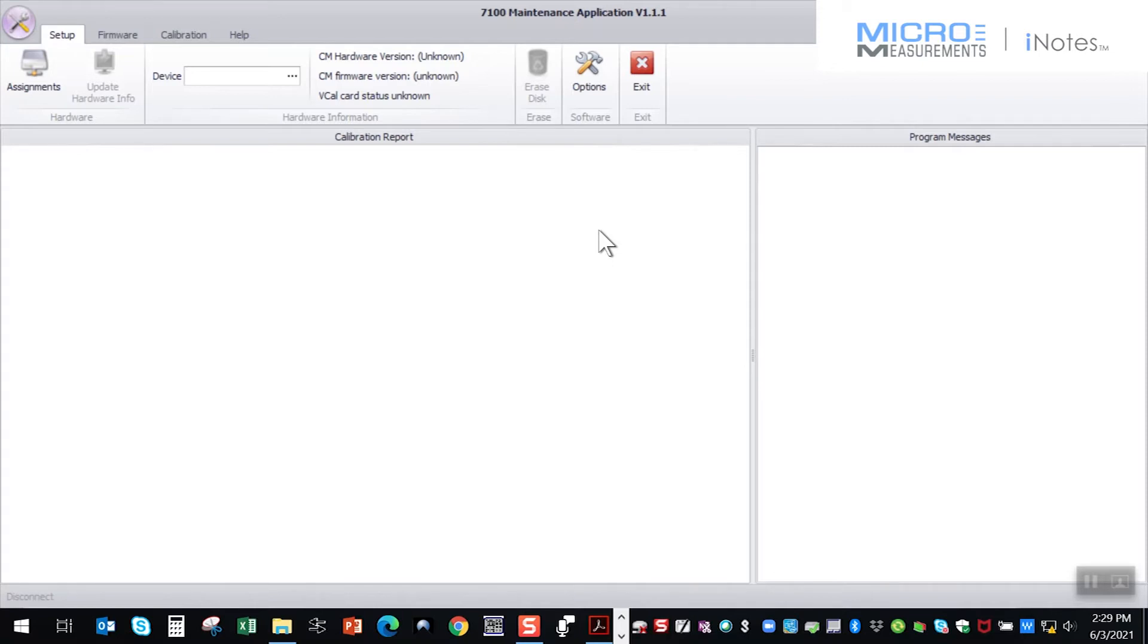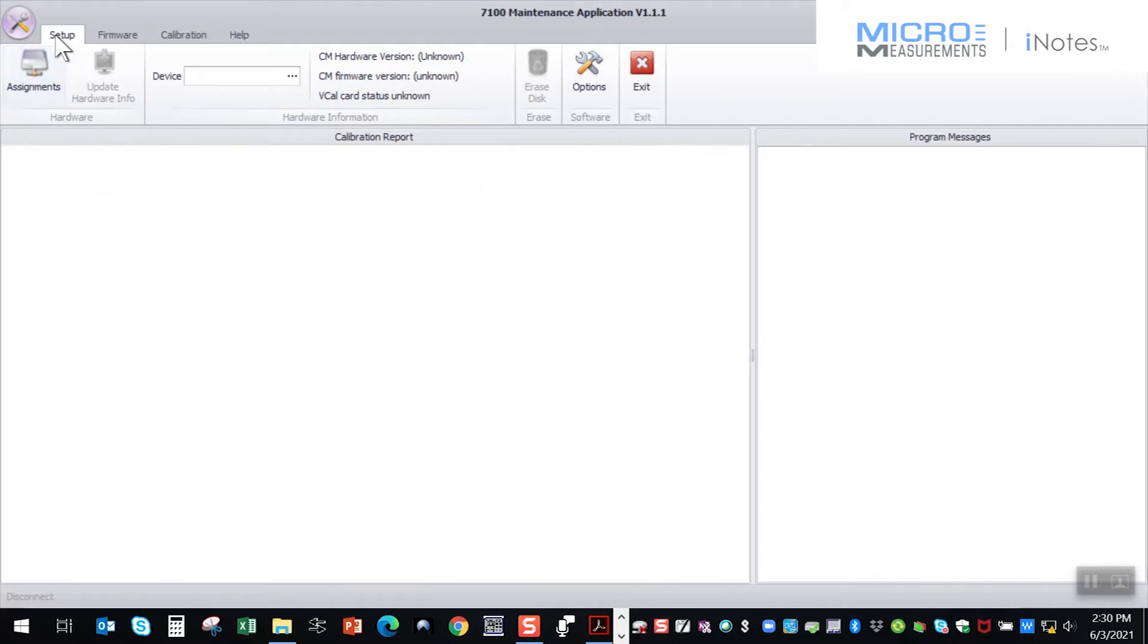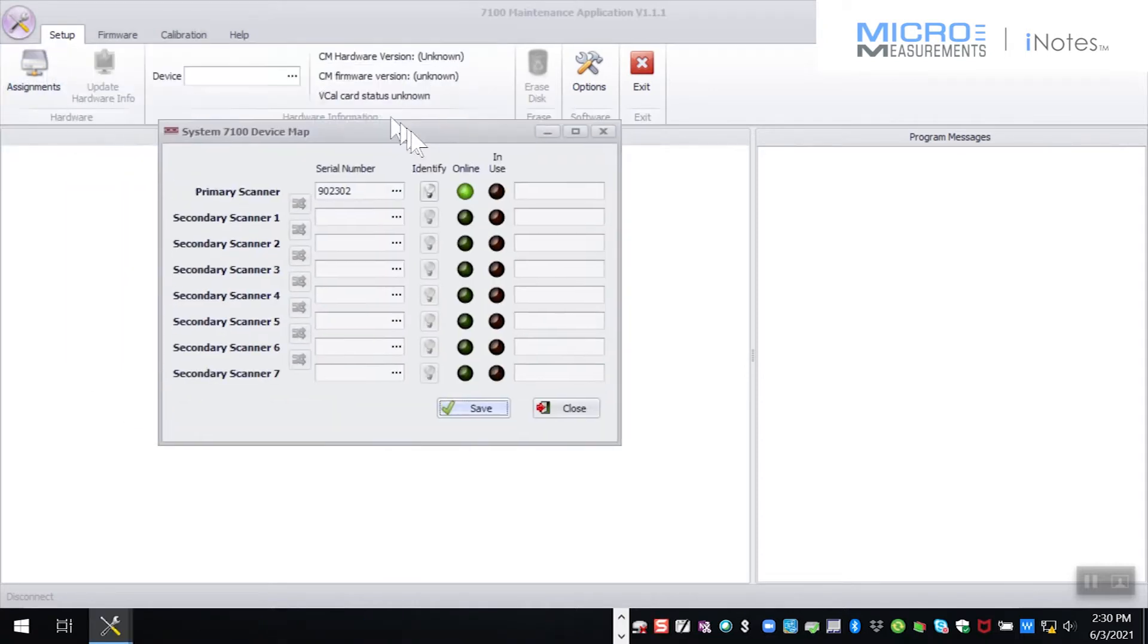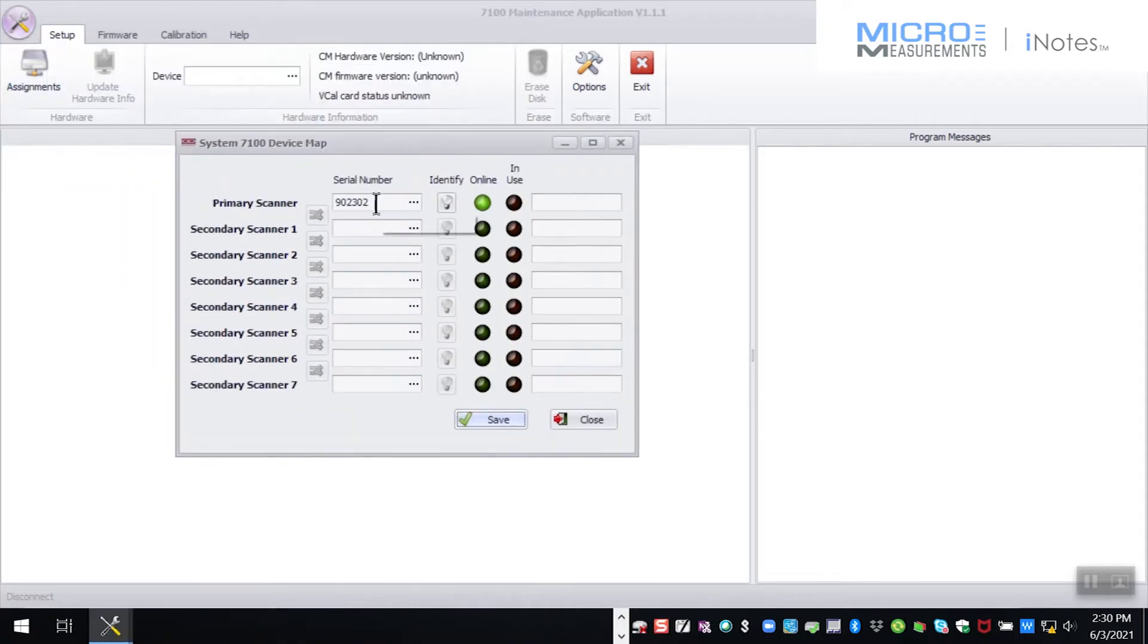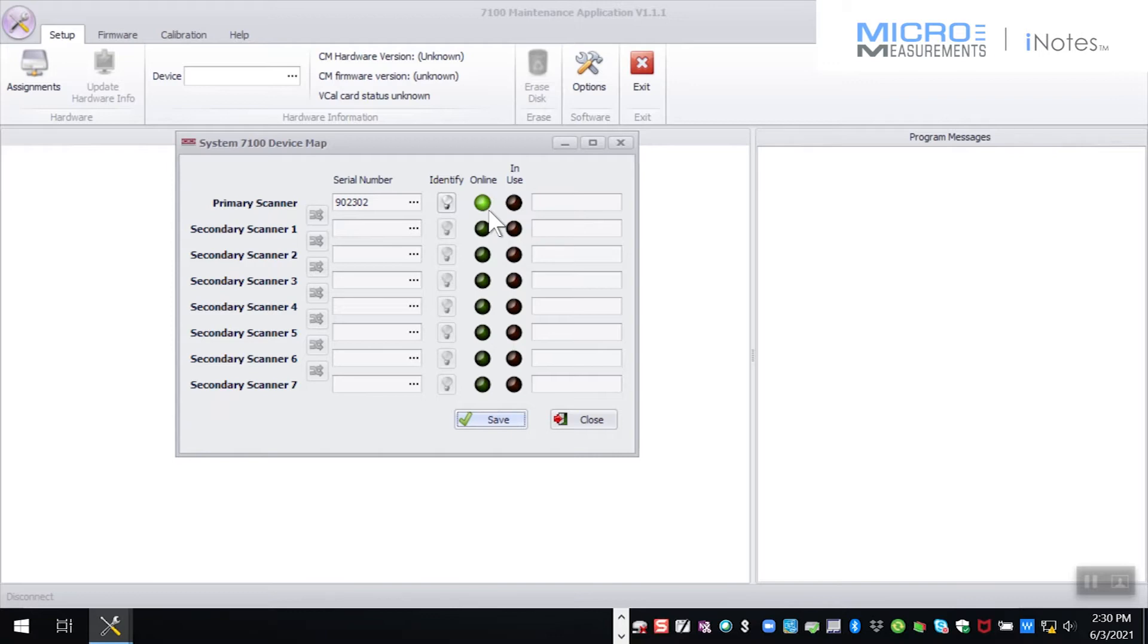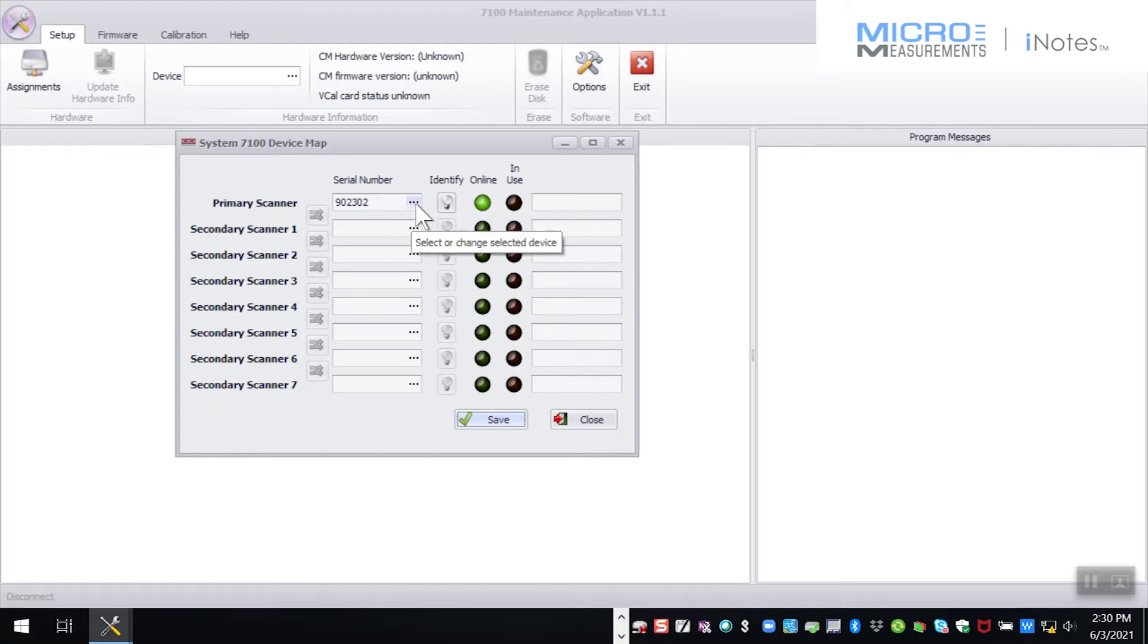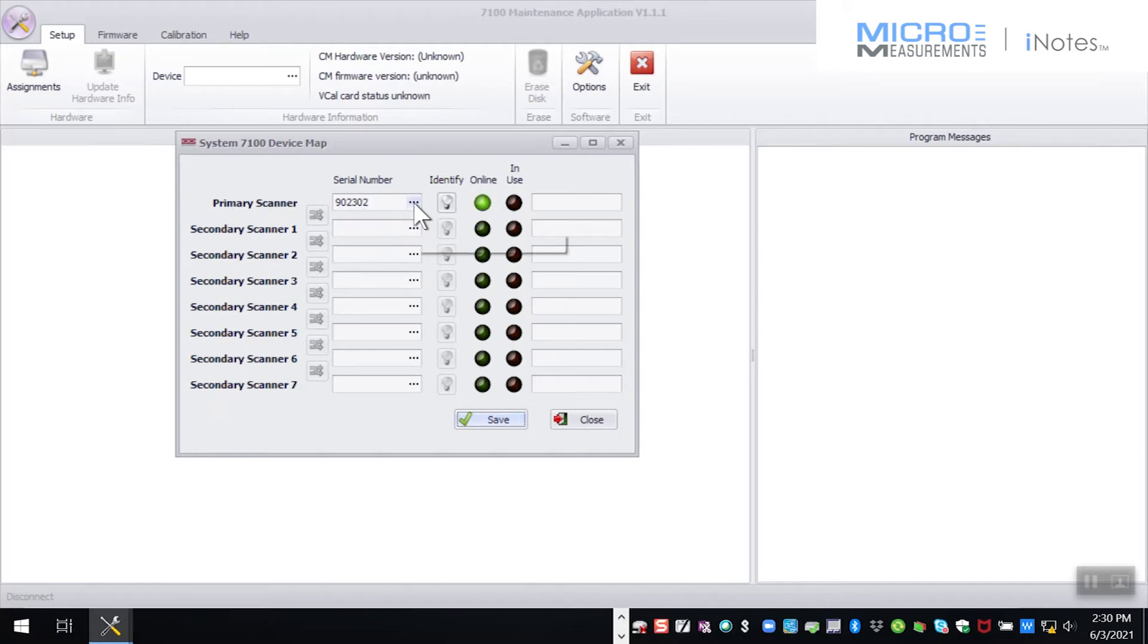And I'll show you a little calibration sequence here. Actually, I'm not sure if it has a VCAL card. I guess we'll find out. We'll find out real quick. But first I need to find the scanner. So here's the big key, the minimal thing that you need to do in order to get StrainSmart software to work. Under the first tab that says Setups, there is an Assignments button. And the Assignment button by default has a scanner number in there, a serial number for a scanner in there. Oh, and it happens to be the one that we got. So I guess we'll play the lottery. Purely by luck we've got a scanner hooked up that's already connected.